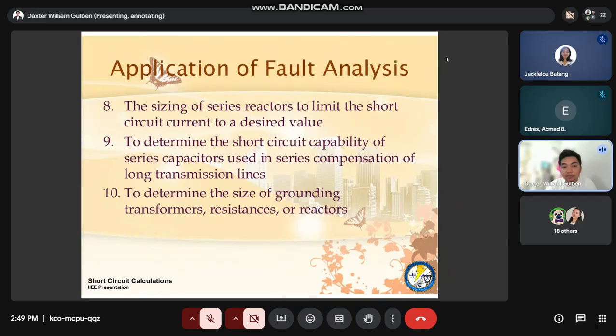Number 9, determine the short circuit capability of series capacitors used for series compensation in the long transmission lines. So ini similar ni siya sa number 8, because of the compensators. Supposedly compensator is used to support voltage quality, no, and then the same time pong ma-improve ang short circuit capability. Number 10 is the determination of the grounding transformers, resistances, and reactors. So with the use of the short circuit analysis, you have this information. We can specify the size of the grounding transformers sa tuang linya. Okay, so muna yung mga applications sa tuang short circuit analysis.